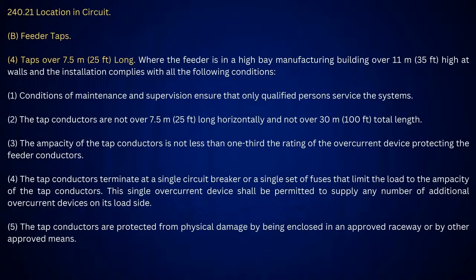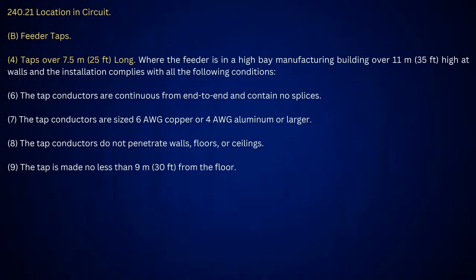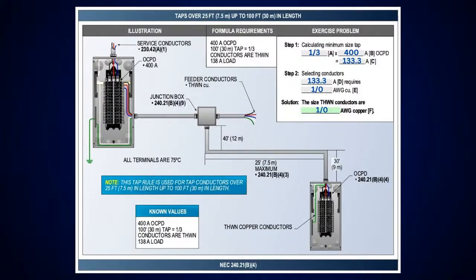All right. Now look at this. This is taps over 25 foot up to 100 foot. And if you look at B42, it tells you not over 100 foot long. But the interesting part is in B43, it says not less than what? A third. So this goes back to what I said earlier. Anything that's 10 foot or less, divide by 10. Everything else you take at a third for the tap, except where I have a transformer. It's still a third on the primary, a third on the secondary, but I've got to have the ratio of the transformer also. I'm not going to go through all that. I'm just trying to show the difference.